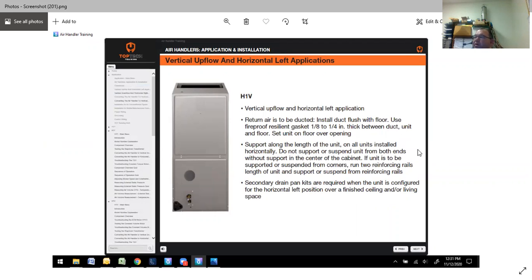Vertical upflow: return air is to be ducted flush with the floor. There again, use the fireproof gasket between the duct, unit and floor. Support along the length of the unit on all units installed horizontally. Do not support or suspend the unit from both ends without support in the center. If the unit is supported or suspended from the corners, run 2 reinforcing rails to support the center as well.